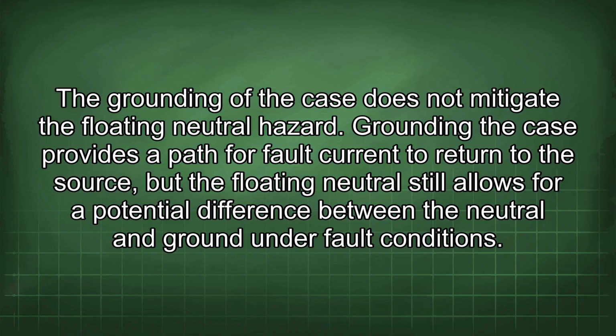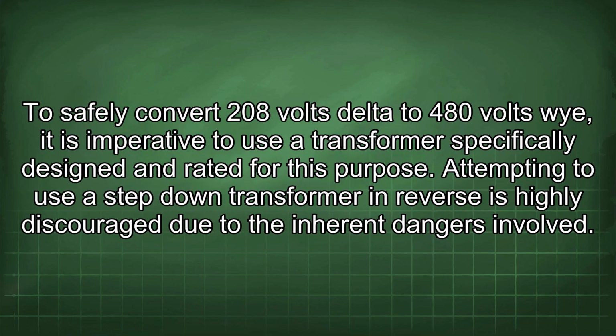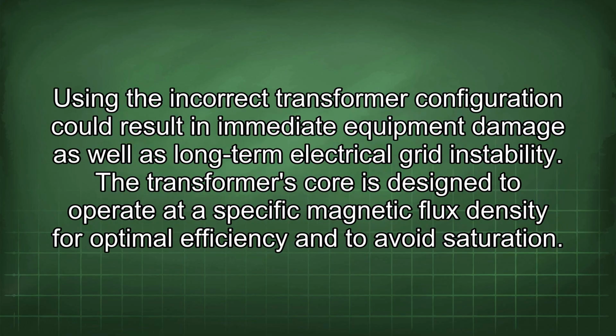Grounding the case provides a path for fault current to return to the source, but the floating neutral still allows for a potential difference between the neutral and ground under fault conditions. To safely convert 208 volts delta to 480 volts Y, it is imperative to use a transformer specifically designed and rated for this purpose. Attempting to use a step-down transformer in reverse is highly discouraged due to the inherent dangers involved. Using the incorrect transformer configuration could result in immediate equipment damage as well as long-term electrical grid instability.